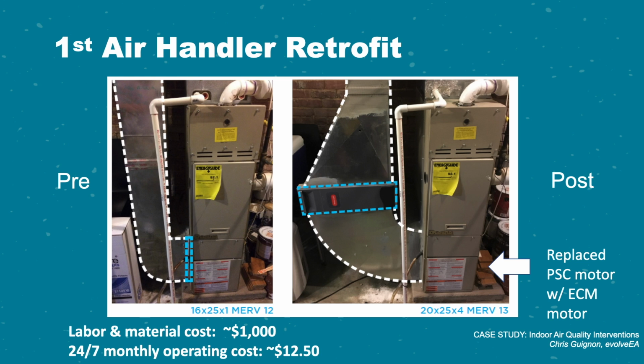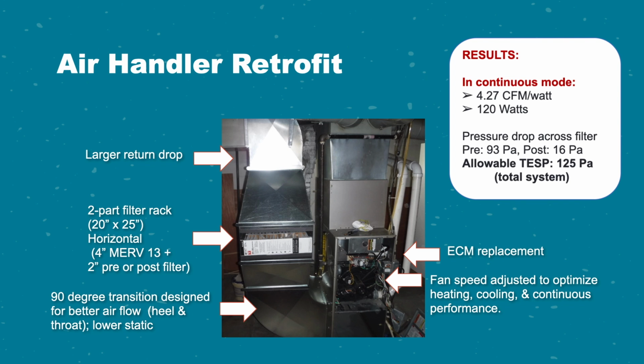That would be lower in a furnace that you bought that had a really good, the better ECM. We're basically using dumb ECMs because that's the only thing you can use as a replacement. But the new furnaces and AC systems that have the upgrade to the best ECM, you could get this cost down to $3 or $4 a month. So really low for 24/7 operation. So another just shot of what we saw. You can come back and look at these slides later.